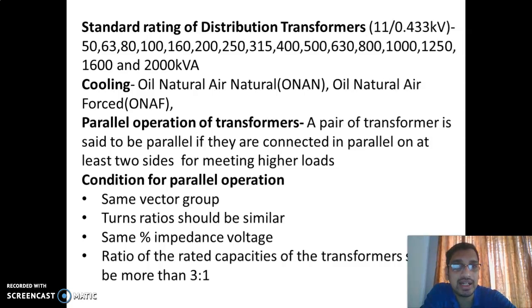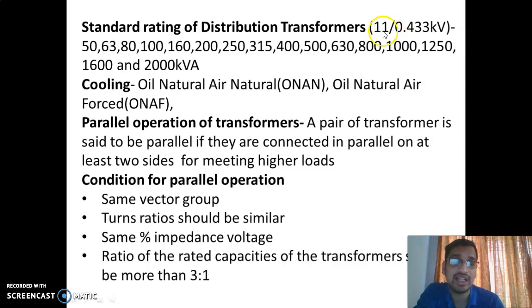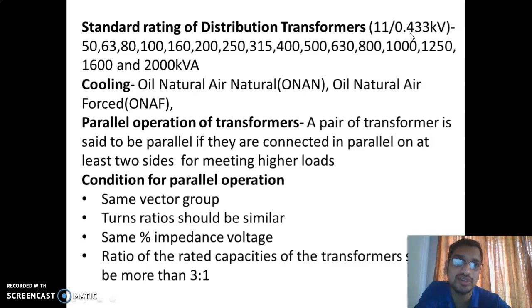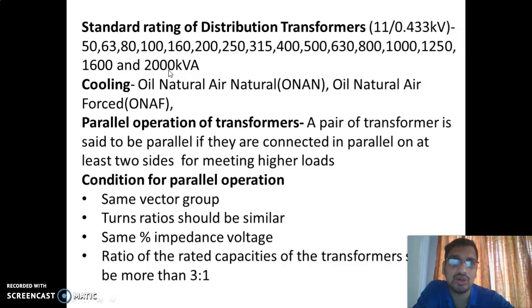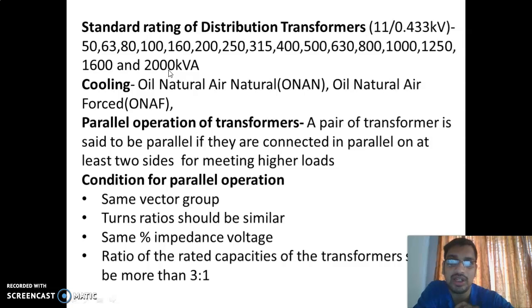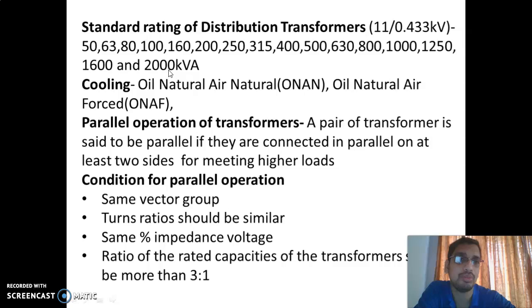Normally in medium type industries, they erect a transformer of 11 kV / 0.433 kV distribution transformer. The standard sizes are 50, 63, 80, 100, 160, up to 2000 kVA. If the maximum demand is above 50 kVA, you must install a distribution transformer of 11 kV / 0.433 kV — that is the statutory requirement. If the maximum demand is above 50 kVA, you get only the HT connection, so you should erect an 11 kV / 0.433 kV transformer.